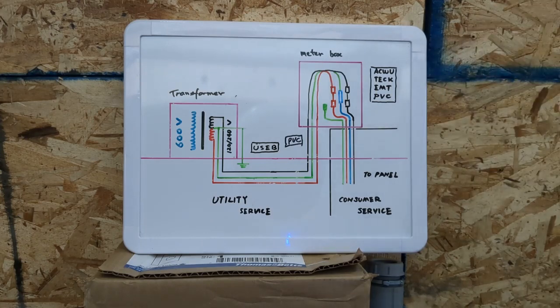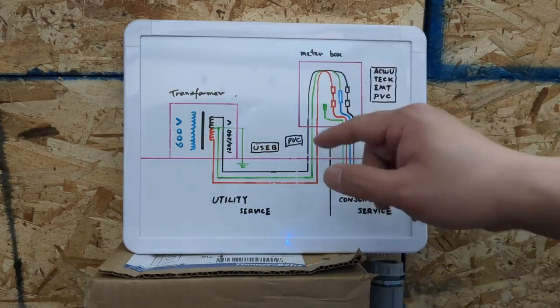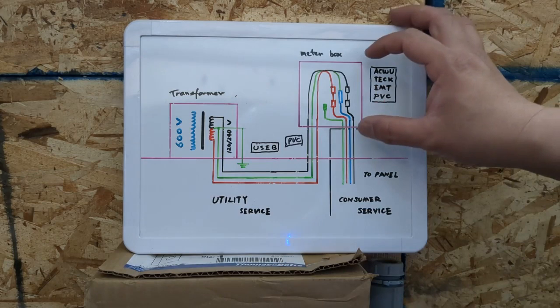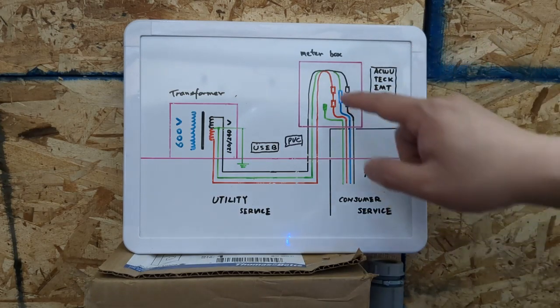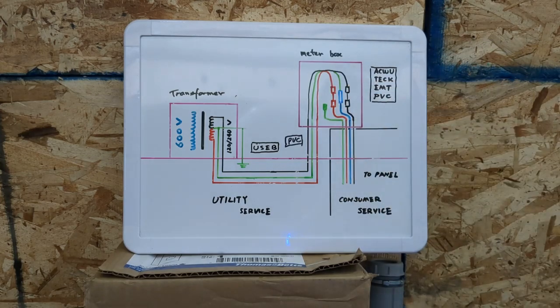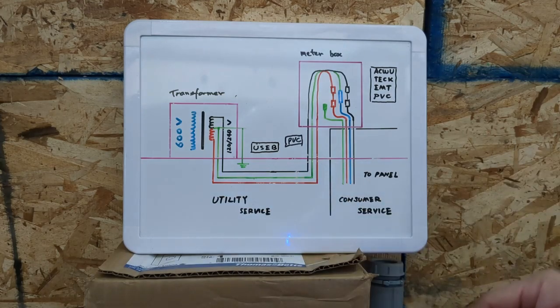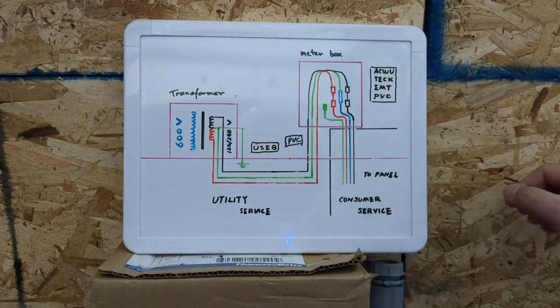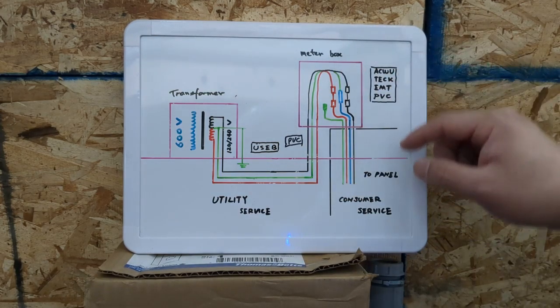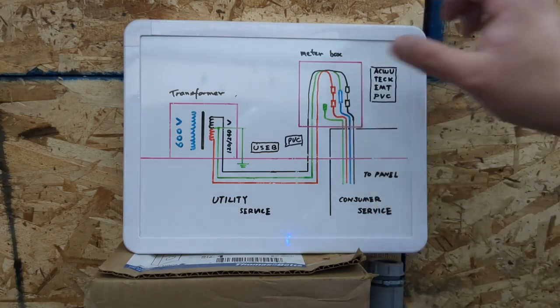From the meter to your main panel, you can run either armored cable — ACWU or TECK cable — or you can run conduit and pull conductors inside of it; you can use EMT or PVC. From the transformer you have only three conductors, but from the meter to your main panel you have four conductors — one extra neutral. When you use the USE-B, the utility company uses the bare copper ground as the neutral, so you connect your neutral from your panel to their ground, then use your own ground to bond the meter box.